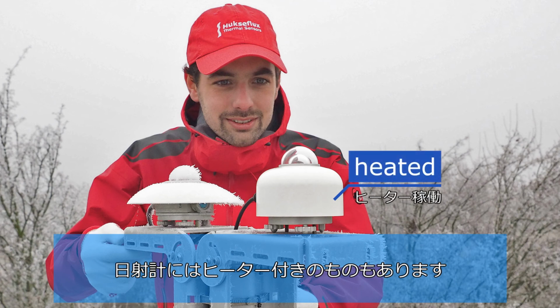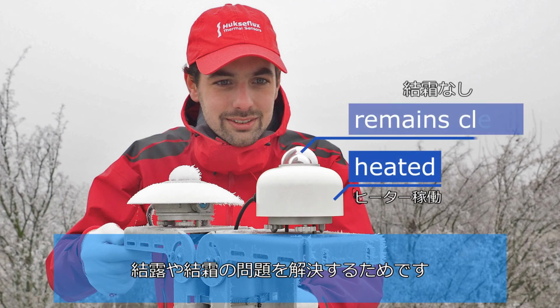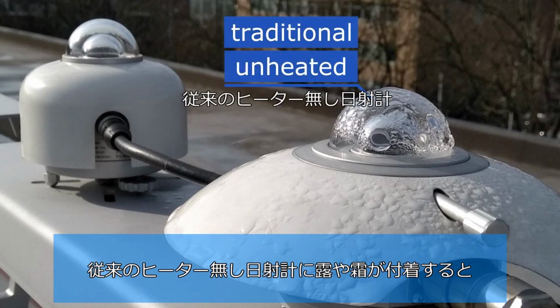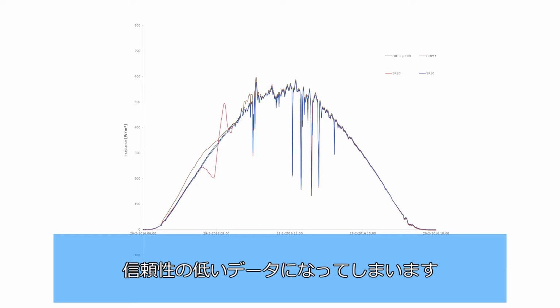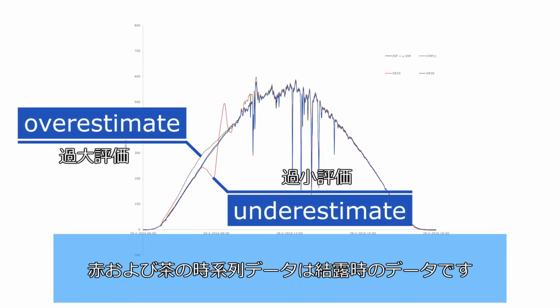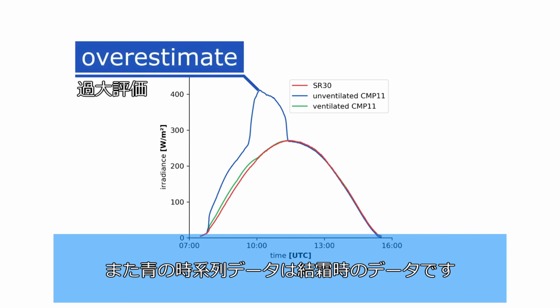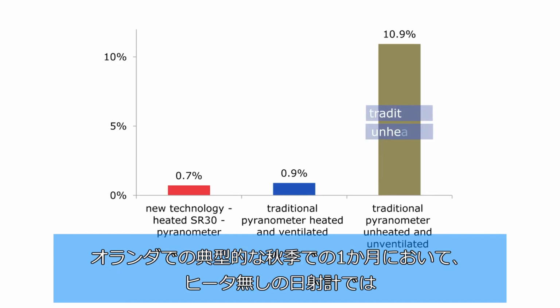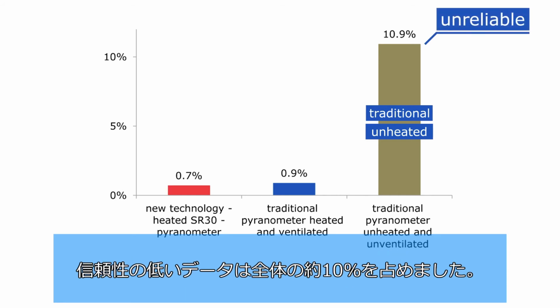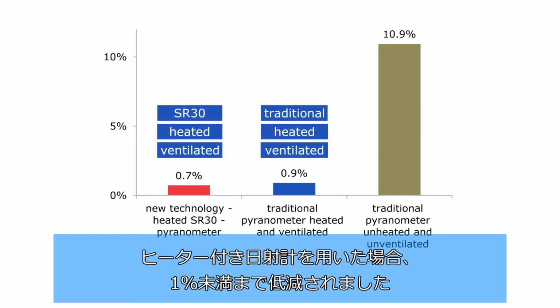Some pyranometers are heated. Heating solves problems with dew and frost deposition. With dew and frost deposited on traditional unheated instruments, you get unreliable data. For example, these red and brown lines for a dew event, or this blue line for a frost event. With unheated instruments and a typical autumn month in the Netherlands, you get unreliable data for about 10% of the total time. With heated instruments, this 10% is reduced to just 1%.